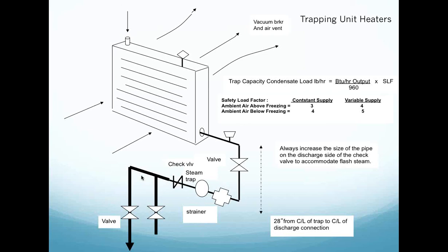You'll notice on the bottom of this, prior to that steam trap, the steam trap is the circle on the bottom, that the item just prior to that is the strainer. But I show 28 inches from the center line of that bottom header of that unit heater to the actual center line of the steam trap.